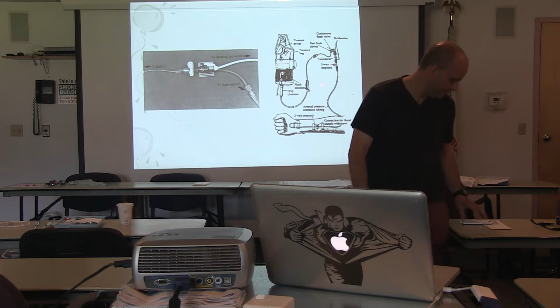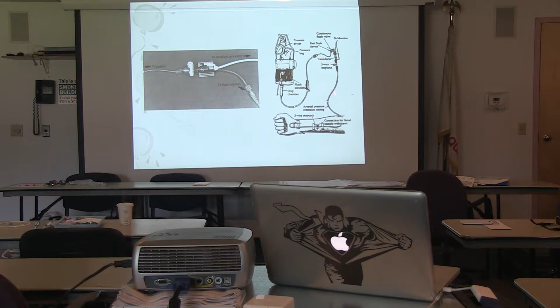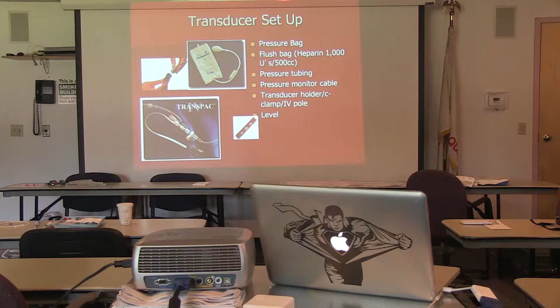And what you'll have is a pressure bag that you're going to keep inflated at 300 millimeters of mercury, and then your transducer and your three-way stopcock. You just turn it back and forth, and it goes down to the patient's artery. Okay? To set one up, you're going to have a pressure bag, pressure tubing, which is rigid, not like regular IV tubing, a transducer, holder, C-clamp, IV pole, and a level.